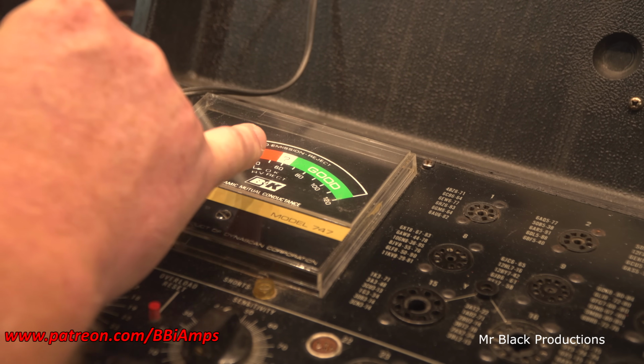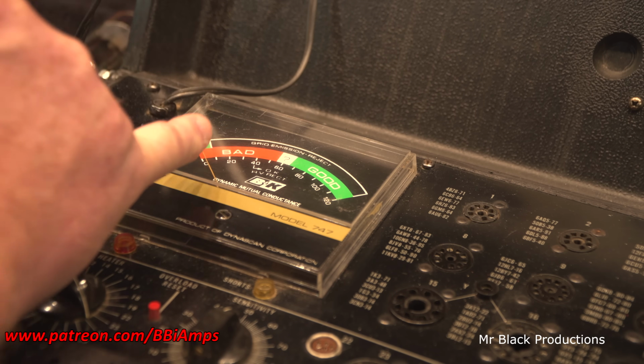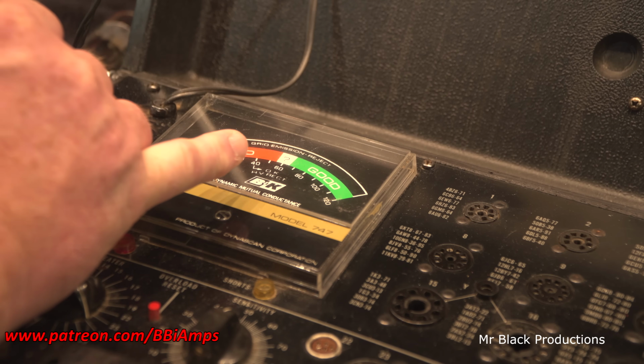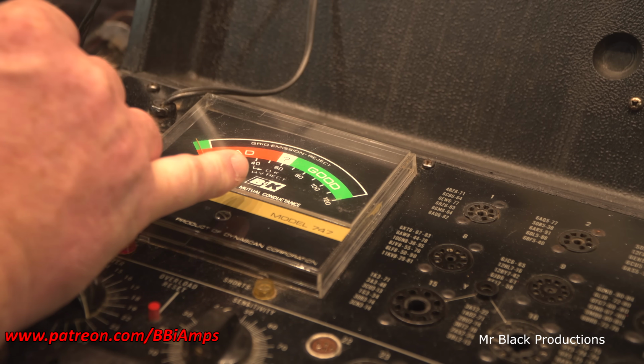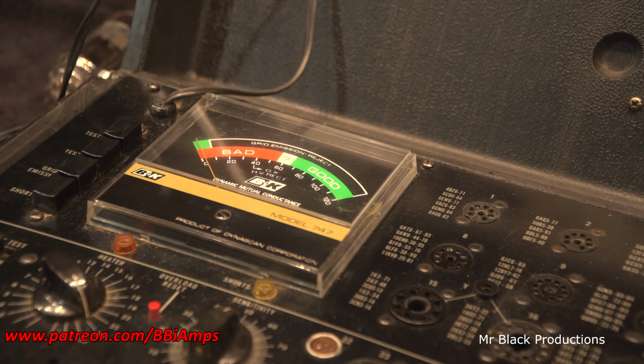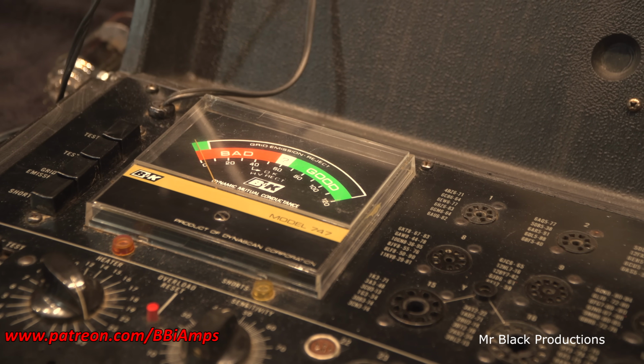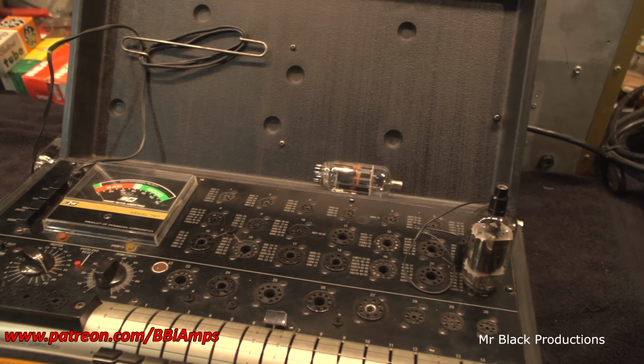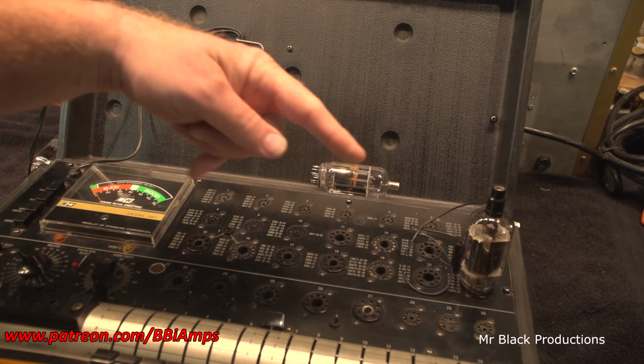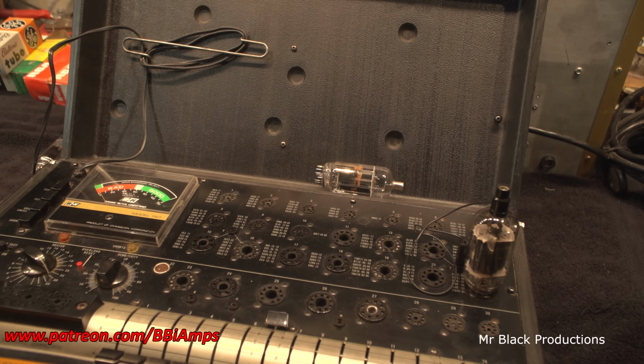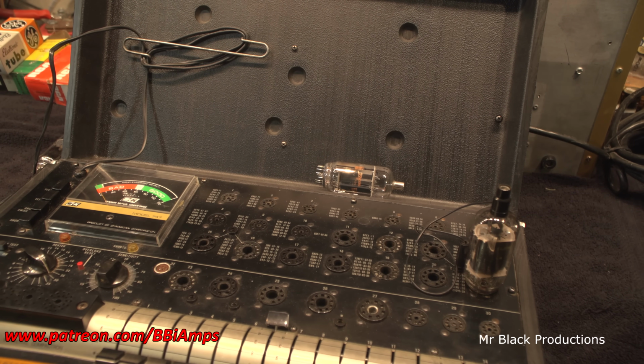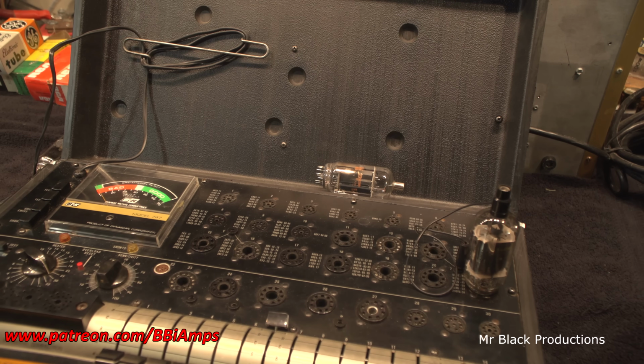Once we get below the 55% mark on the scale, it says okay, high voltage reject. When you get that low with the gain of the tube, you run into a problem where you have to worry about the tube's high voltage, the anode and the cathode being able to cross over to each other on the inside of the tube and cause a high voltage short.